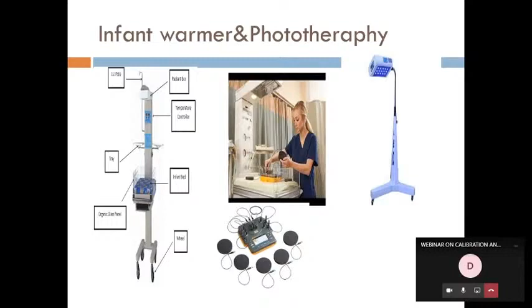If you are placing this machine instead of a baby, you get a value. Okay, for example, you set 40 degrees Celsius in the warmer, the machine has to show almost 39 or 40 degrees on this analyzer. Okay, if not, you need to calibrate the machine. Instead of a baby and the skin temperature probe, you keep this machine. This analyzer is nothing but a digital thermometer or digital temperature calibrating analyzer.